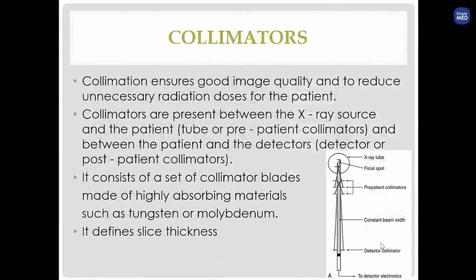Going to the collimator, the collimator will give better image quality by reducing the radiation dose to the patient. We have two types of collimator: one is the pre-patient collimator, and the other is the post-patient collimator.